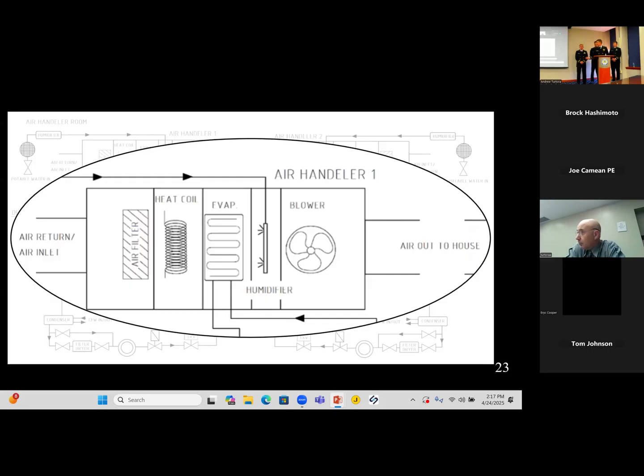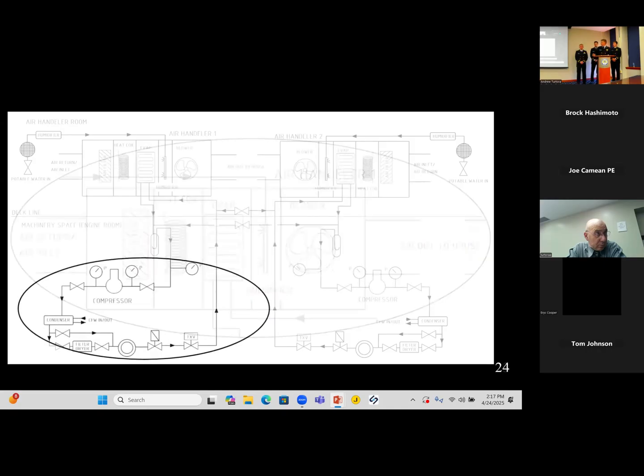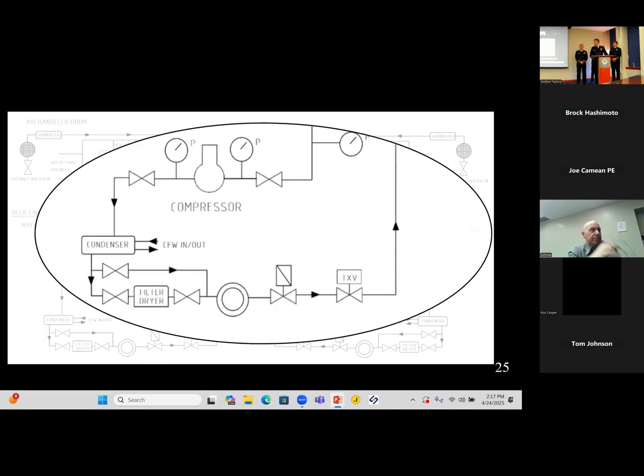And it goes through a humidification unit, which uses the potable water system to humidify the air when it's necessary. And then it goes through a blower system, and then the air out to the house. All right, so that's air inlet, air filter, heating coil, evaporator, humidifier, blower, air out. And then in the engine room, we have your basic refrigeration system, which has compressor, condenser, receiver, and then goes through a filter, dryer, TXV, and then back up to the compressor.